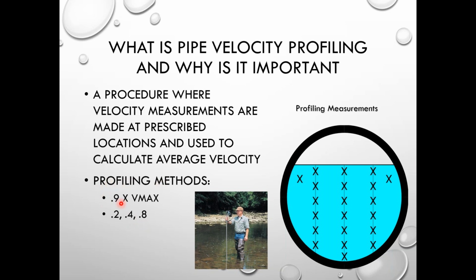And so with our profile methods, we have what's called a 0.9 Vmax and a 0.2, 0.4, 0.8. So the 0.9, it's basically I'll take the probe, I'll stick it down in the flow, I'll try to find the highest velocity, and I'll just times it by 0.9 to give me my average. This has been generally pretty close to an average. And then we can also do the 0.2, 0.4, 0.8, which is basically just taking it and bringing it up a quarter of the way, half of the way, 3/4 of the way, and then figuring out what my average velocity is in there, right? Because you got your pipe roughness coefficients here, you got different solids, that type of stuff. Or if the pipe's turning, you might have different velocities depending on where you're at in the pipe.